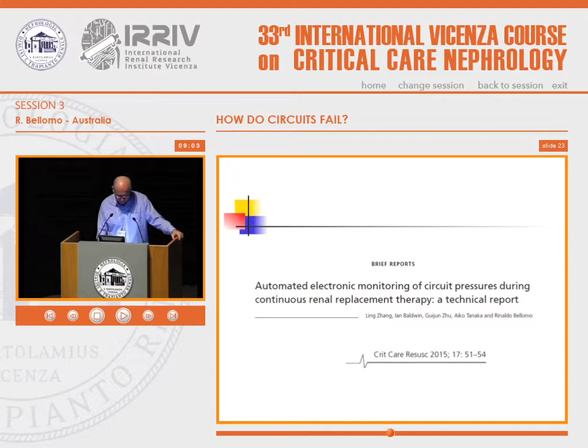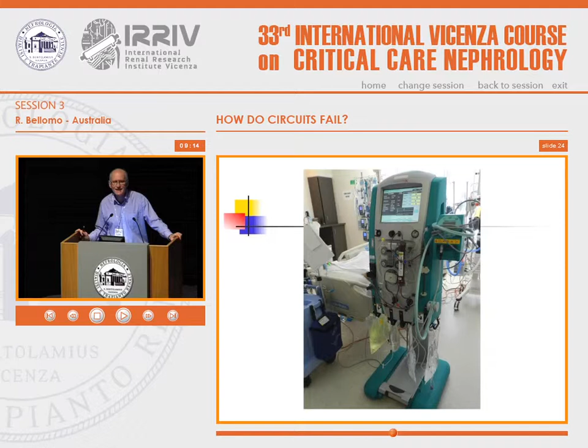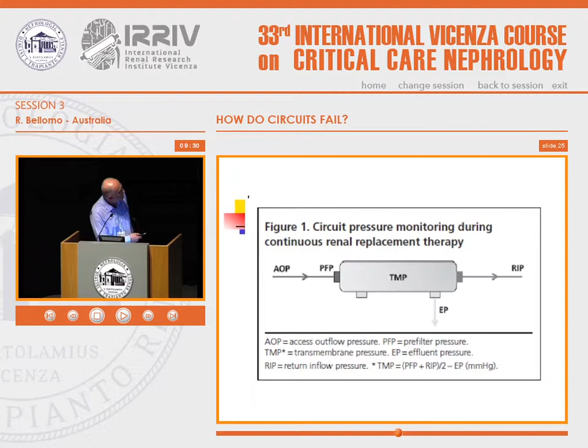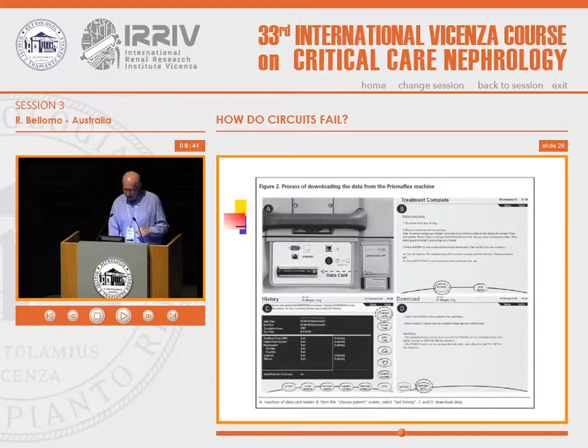And indeed, you can actually have automated monitoring of pressures in different places in the circuit that can tell you very much about what's happening to your filter and circuit as time goes on. And this is the Prisma machine, and you can download from the back of the machine electronically all of the data every minute for the access outflow pressure, the pre-filter pressure, the post-filter pressure, the effluent pressure, and the transmembrane pressure, which of course is calculated. Cool. And that's downloadable, can be displayed graphically, and it gives you something like this.